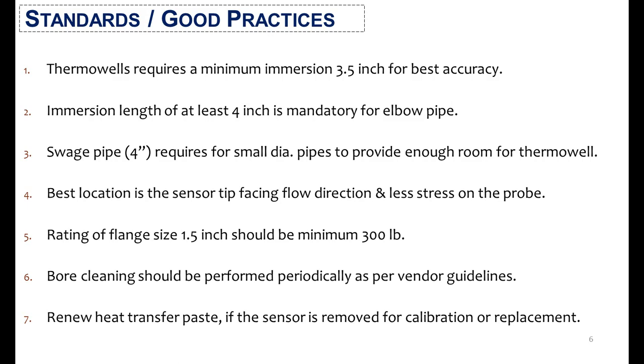There should also be periodic bore cleaning as per vendor guidelines for better accuracy of a thermowell. And there will also be a need to renew the heat transfer paste if the sensor is removed for calibration or replacement.